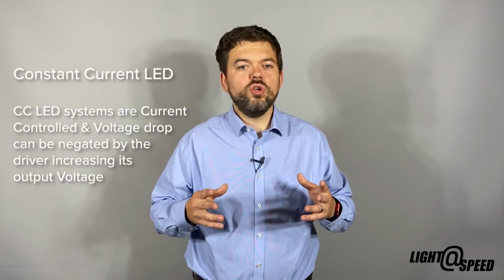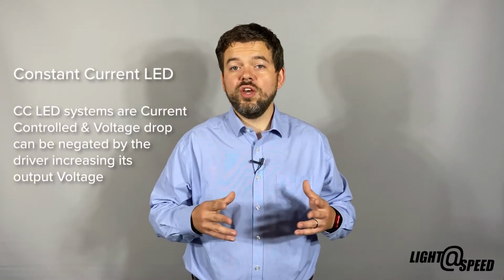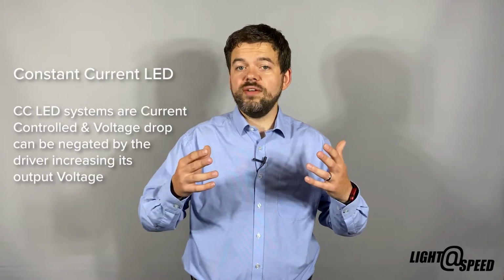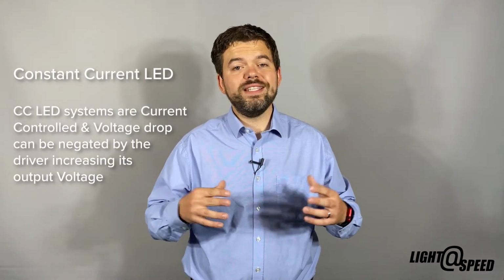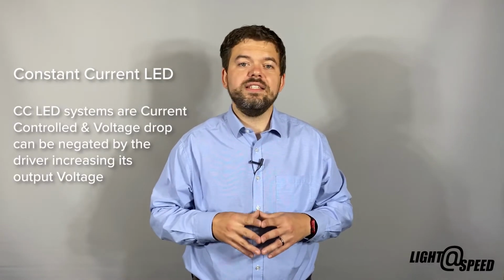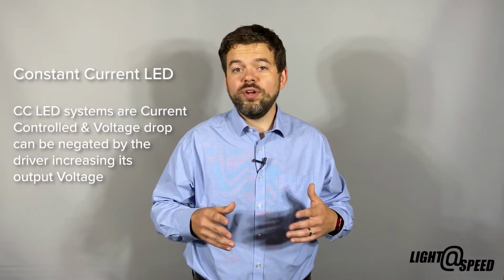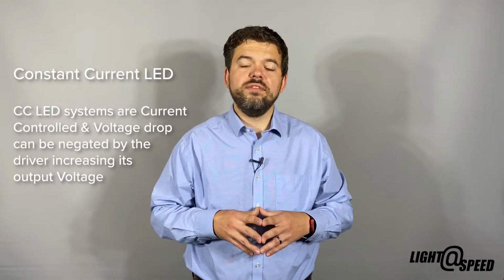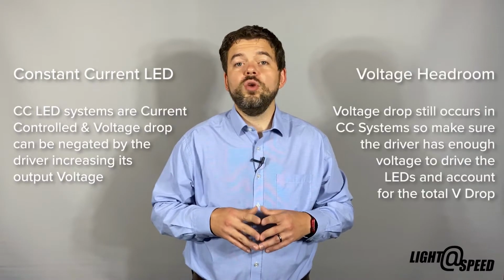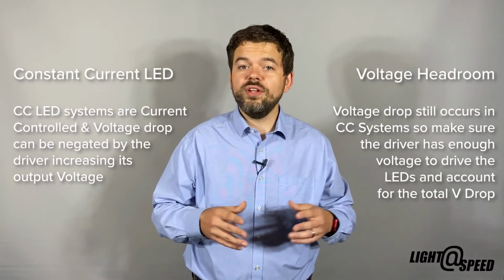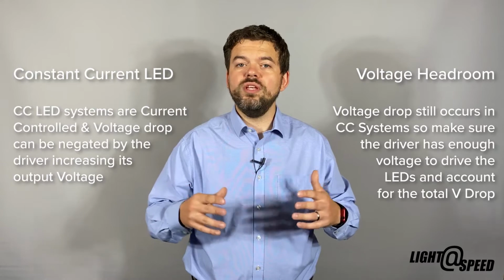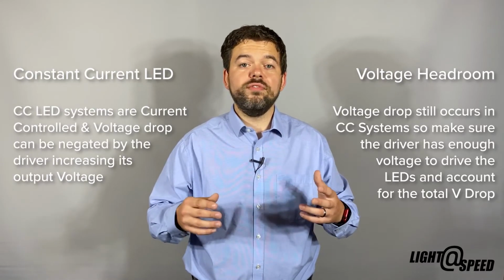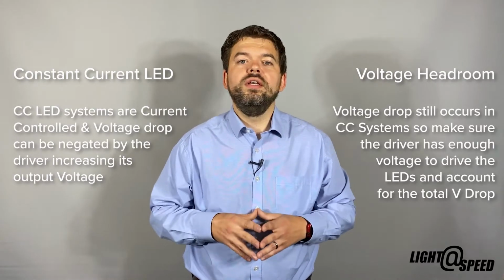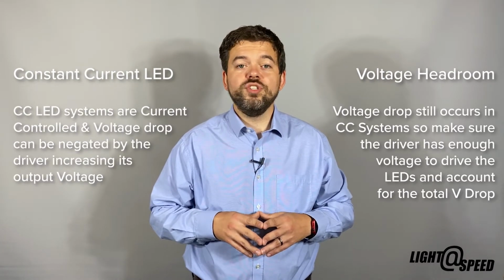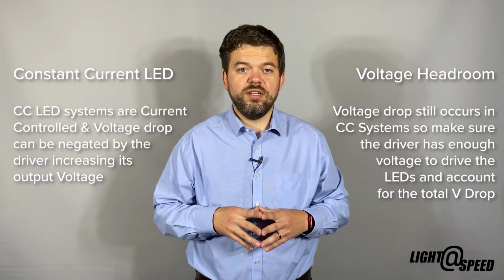Constant current systems do not usually suffer this issue, as constant current drivers can adjust their output voltage level depending on the voltage drop they sense through the cables and the LEDs. They maintain the electrical current level requested by increasing the voltage a bit. The only time voltage drop is an issue with constant current is when the driver doesn't have enough extra voltage after powering the LEDs, often referred to as voltage headroom, to overcome that drop. So just make sure the driver is well specified.